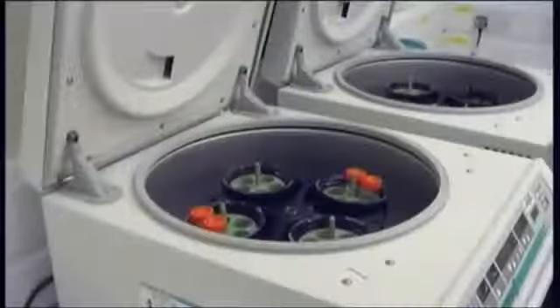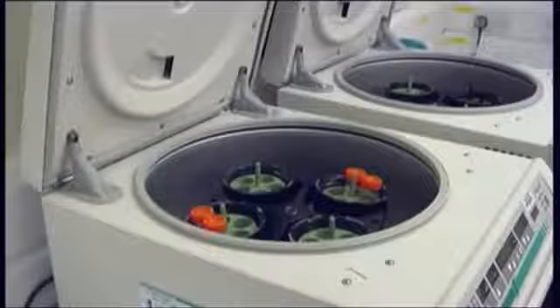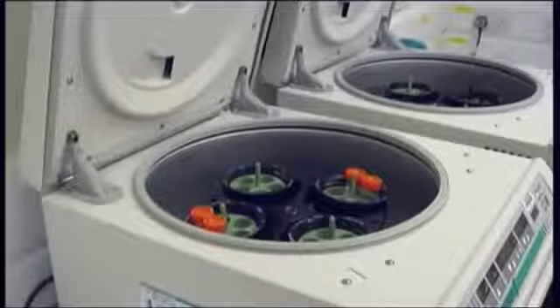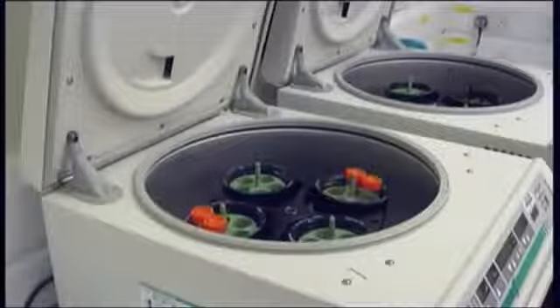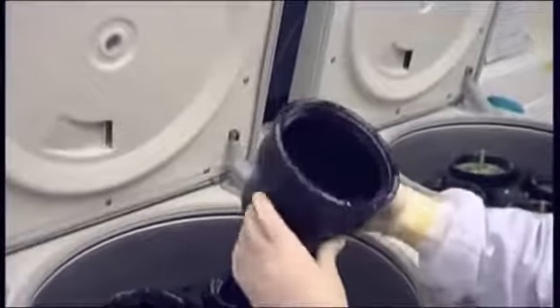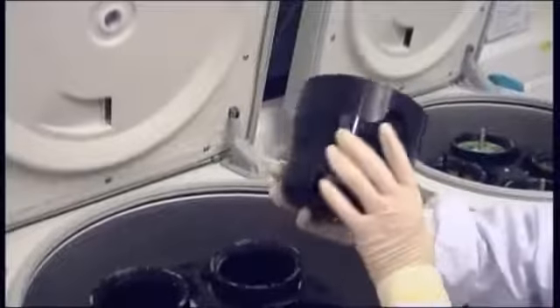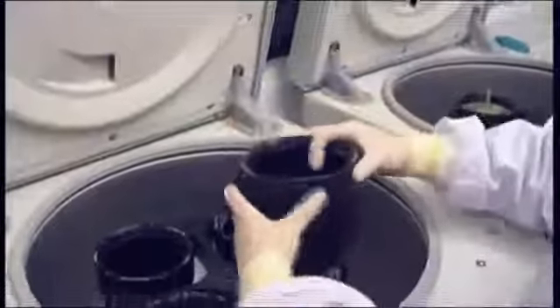Centrifuges. Centrifuges are used to rapidly sediment cells into a pellet, to allow transfer of cells into different media or buffers. A small benchtop centrifuge with controlled braking and rotors, with swing-out buckets and sealed caps, is sufficient for most purposes. Situate the centrifuge where it can be easily accessed for cleaning and maintenance and away from microscopes, which can be affected by vibration.